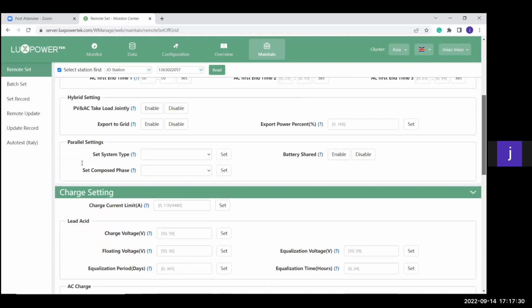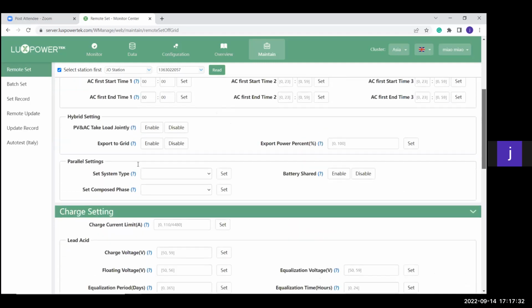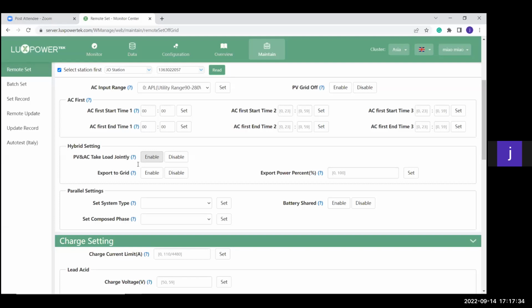Then just remember, if you pick PV AC jointly, then the machine will use PV and AC as far as possible to provide power to the load, even if your batteries are full. If you don't want to use Eskom at all, you disable this function. Then it will use the panels, and if the panels have a shortfall, it will take it from the batteries until the level where it is set at the bottom.